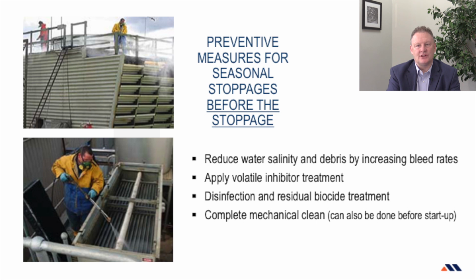The first step usually occurs a few days before the stoppage, where bleed rates must be increased. This will reduce the water salinity and lower the amount of debris and silt that could settle. For example, normal conductivity would be around 1200, and should be lowered down to 500.